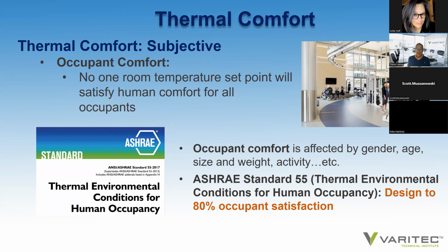Well, the reason for that is because a person's gender, male or female, their age, their size, weight, activity, are they healthy or are they sick? All of these individuals will have different senses of what it is or what conditions contribute to their thermal comfort. Consequently, because of the subjective nature of thermal comfort, ASHRAE Standard 55 states that an HVAC system is doing its job if a building can maintain 80% of occupant satisfaction.